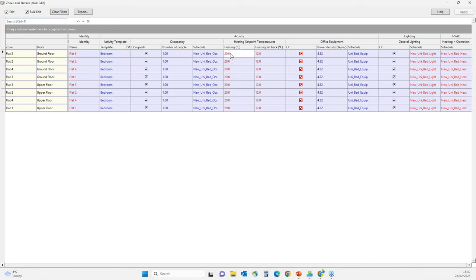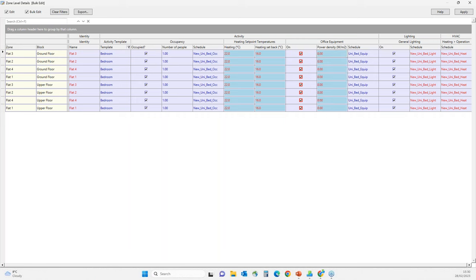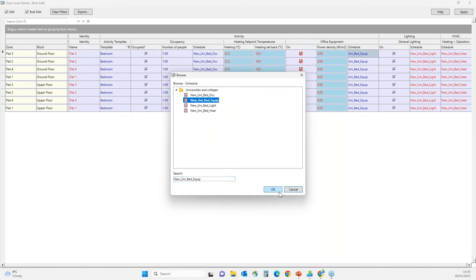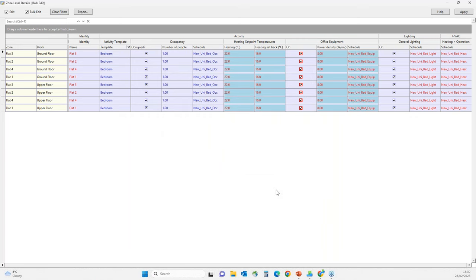For the rest of the data, I will edit them in bulk. Heating set point temperature I'll change to 22 degrees, set-back to 16. Equipment power density to be 8 watts per meter square. I also need to change the equipment schedule to one I have created which is more representative of expected energy use in the building. Besides this, I have also updated hot water demand, auxiliary energy loads, along with heating operation schedule, cooling schedules, and lighting gains in the model.